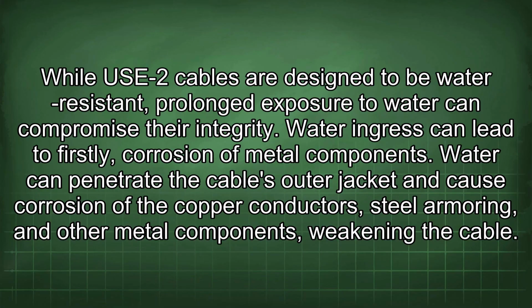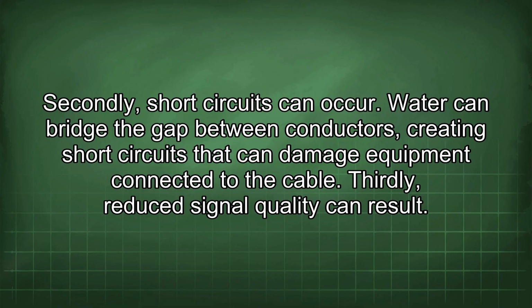While USE-2 cables are designed to be water resistant, prolonged exposure to water can compromise their integrity. Water ingress can lead to, firstly, corrosion of metal components. Water can penetrate the cable's outer jacket and cause corrosion of the copper conductors, steel armoring, and other metal components, weakening the cable. Secondly, short circuits can occur. Water can bridge the gap between conductors, creating short circuits that can damage equipment connected to the cable.